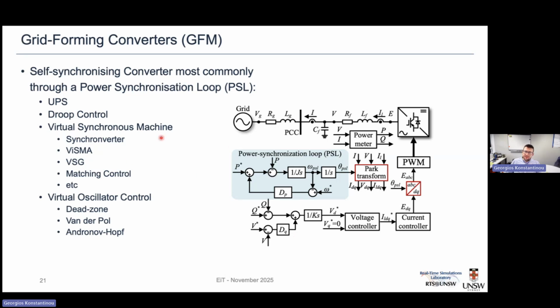This means different ways of doing that: synchroverters, virtual synchronous machines, VSGs (virtual synchronous generators), matching control, and so on, or an internal time-based synchronization method based on virtual oscillator control. All of them effectively end up at the same common point: generating an internal reference for the phasor, this voltage reference, and this internal angle in the grid forming converter, that allows you to effectively regulate what happens as you connect this inverter to the rest of the network.